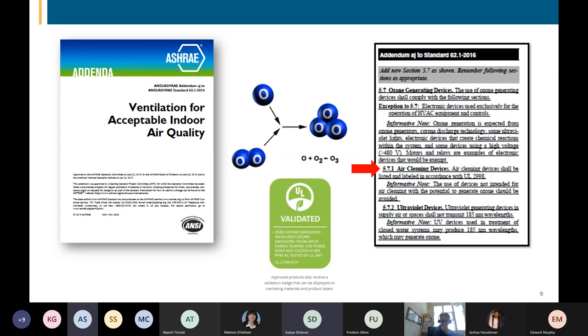Yes. The question is, can there be too many ions in the space? That's a good question. The studies and efficacy that I have read so far do not lean in that direction. There are no specific ion concentration codes or standards that I'm aware of anywhere other than the Russian Federation. The Russian Federation does mandate minimum and maximum ion concentrations in built environments throughout Russia. Those concentration levels are a minimum of 400 ions per cubic centimeter, positive and negative, so a total of 800 ions per cubic centimeter minimum, up to 100,000 ions per cubic centimeter positive, 100,000 ions per cubic centimeter negative, for a total of 200,000 ions per cubic centimeter.